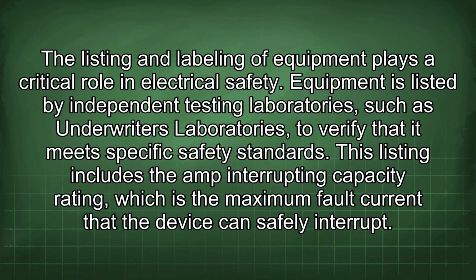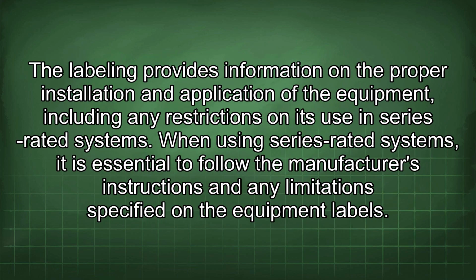The listing and labeling of equipment plays a critical role in electrical safety. Equipment is listed by independent testing laboratories, such as Underwriters Laboratories, to verify that it meets specific safety standards. This listing includes the amp interrupting capacity rating, which is the maximum fault current that the device can safely interrupt.